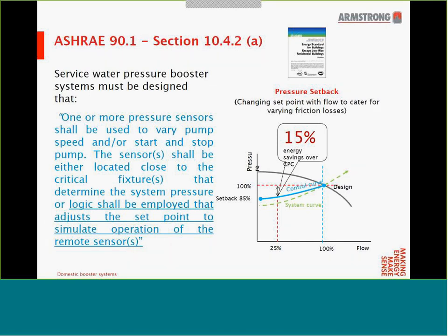Traditionally, all boosters come with one sensor at the suction side and one at the discharge side. Section 10.4.2A calls for feedback control by placing the sensor at the critical fixture at the top of the building, factoring in actual friction losses rather than hypothetical calculated ones. ASHRAE acknowledges it's not always feasible to run wires to place the pressure sensor at the critical fixture at the top of the building due to the cost of running conduits. This clause also allows software logic to simulate the change in friction losses as flow changes — called pressure setback — a very common feature in booster packages.